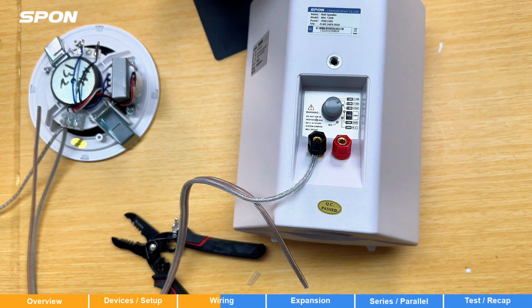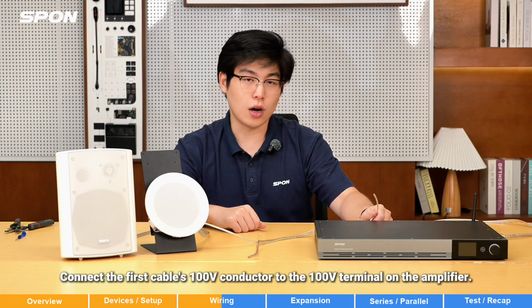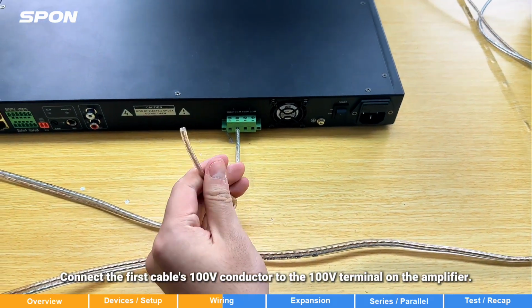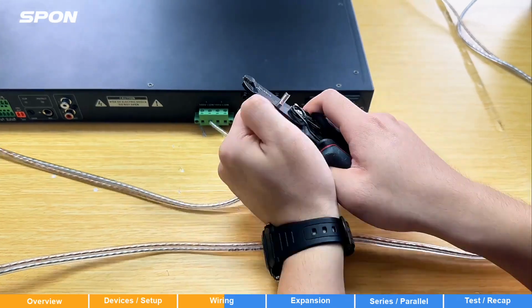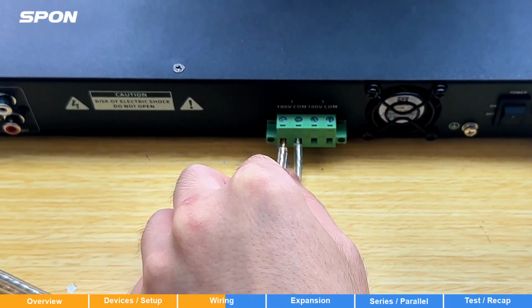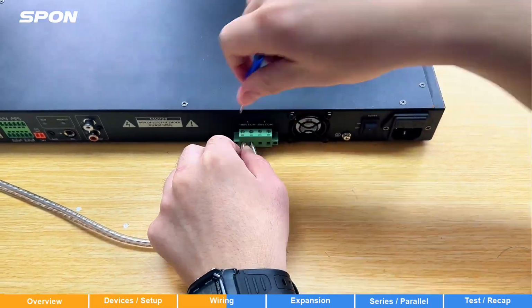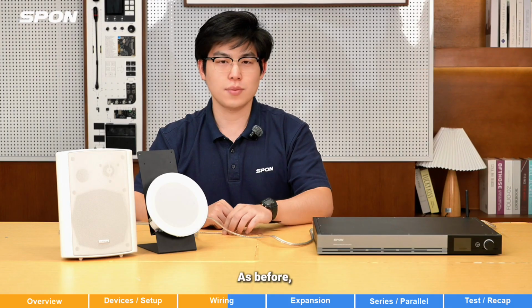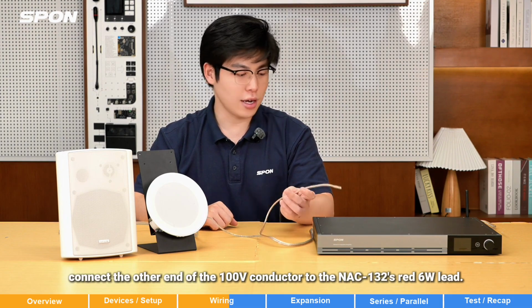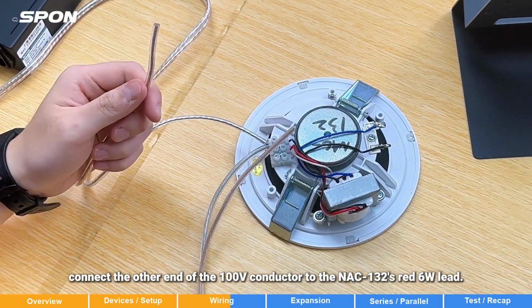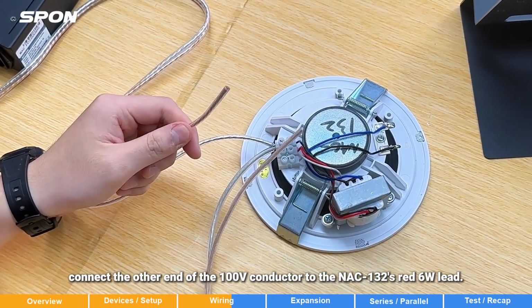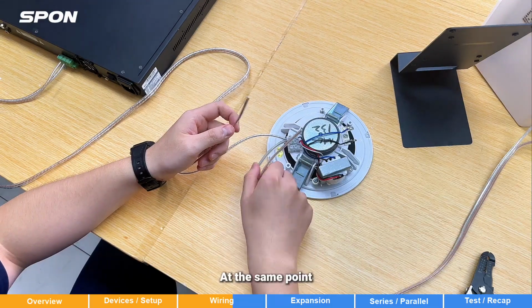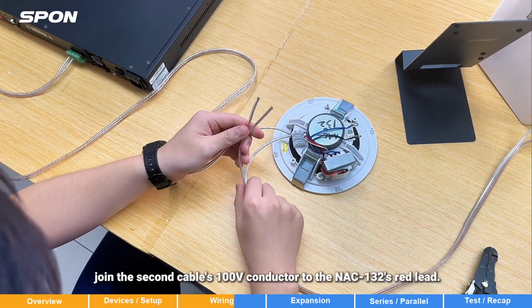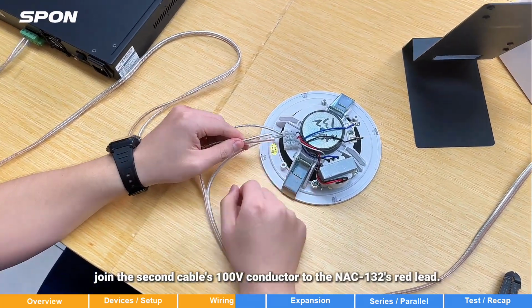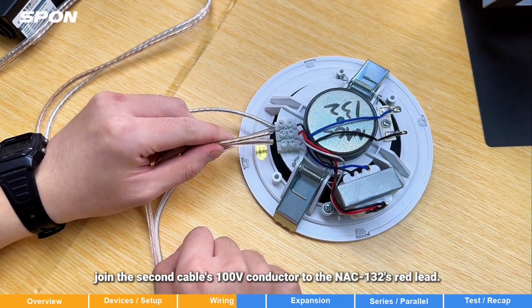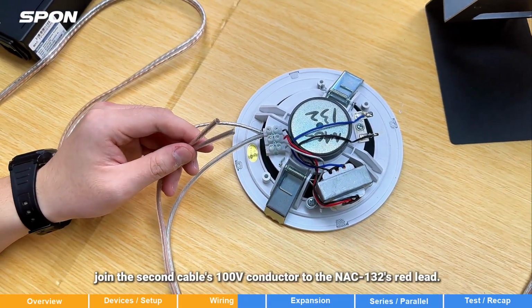Connect the first cable's 100 volt conductor to the 100 volt terminal on the amplifier. Same as before, we need to connect the other end of the 100 volt conductor to the NAC-132's red conductor, which is for 6 watts. And at the same time, combine the second cable's 100 volt conductor together into the red conductor of the NAC-132.